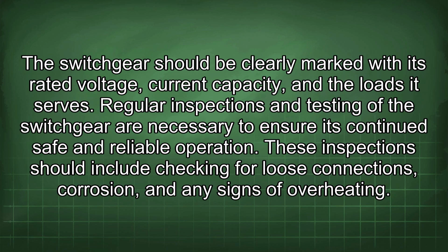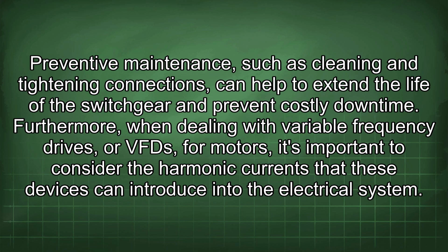The switchgear should be clearly marked with its rated voltage, current capacity, and the loads it serves. Regular inspections and testing of the switchgear are necessary to ensure its continued safe and reliable operation. These inspections should include checking for loose connections, corrosion, and any signs of overheating.